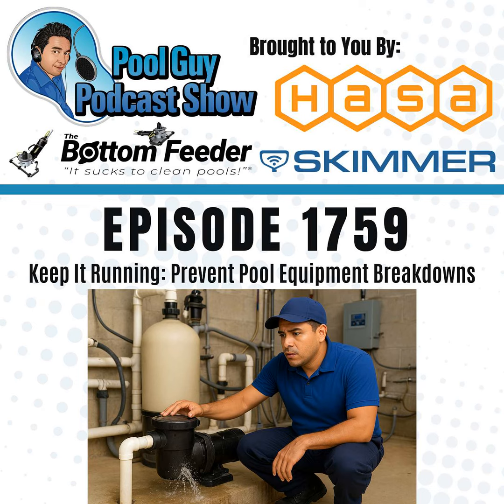I'm not an electrician, but I would imagine that's what's causing it. So keep an eye on those older pumps, because the capacitor will go out and you have to replace them sometimes yearly or every 6 months. I've had that happen as well. And then, of course, you have the bearings wearing out in the motors. Now, the nice thing about variable speed pumps is that they seem not to have this problem very often.